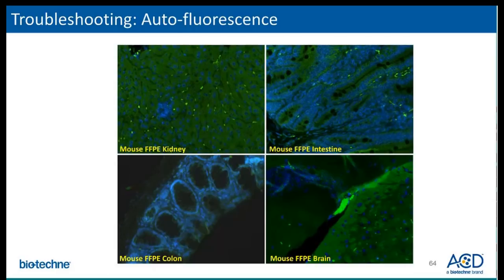One known issue with the fluorescent assay is that due to the long fixation time, FFPE samples are prone to inherent autofluorescence, which poses challenges for image analysis. You can use FFPE if you have background correction software to reduce autofluorescence; alternatively, we have developed the multiplex fluorescence V2 assay that helps address this issue. If you are still experiencing autofluorescence issues, please contact technical support.